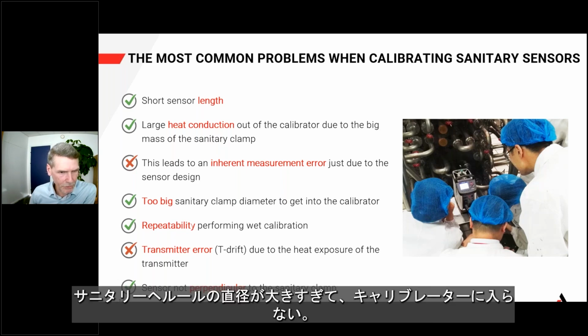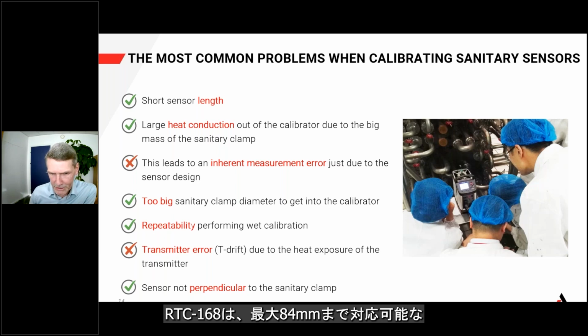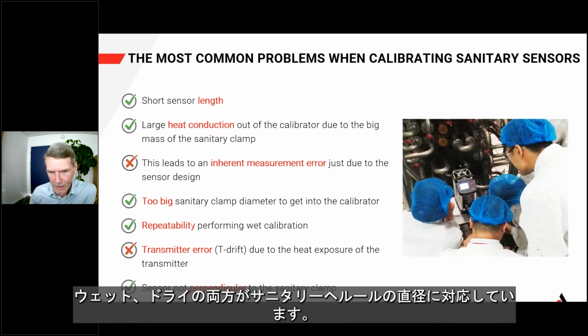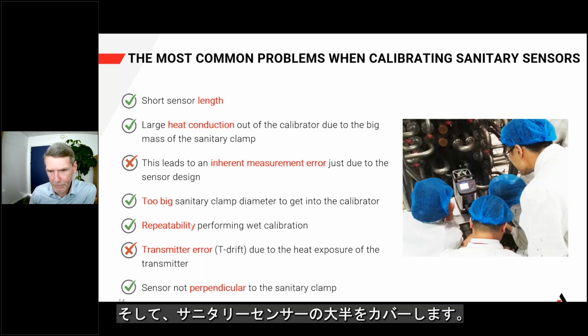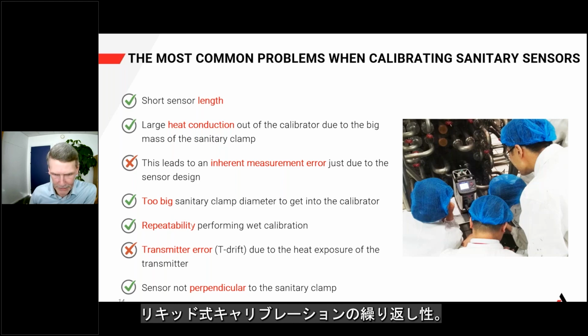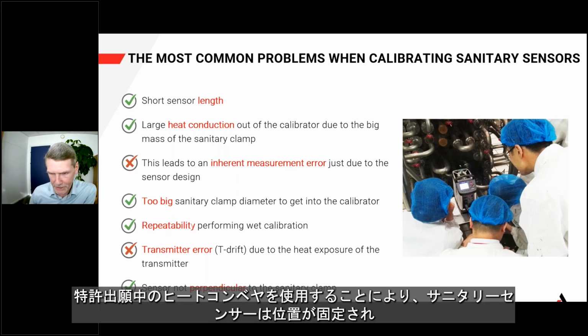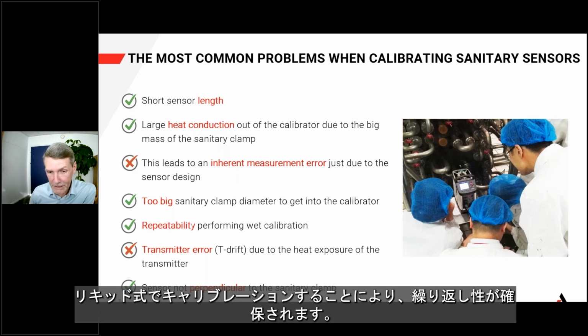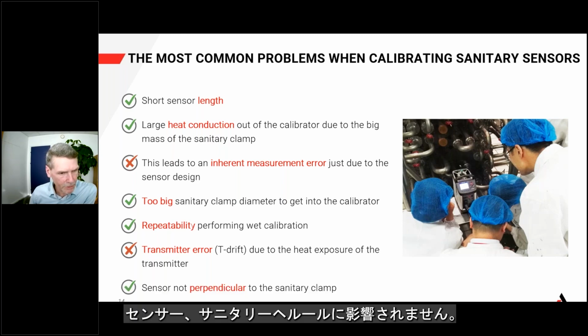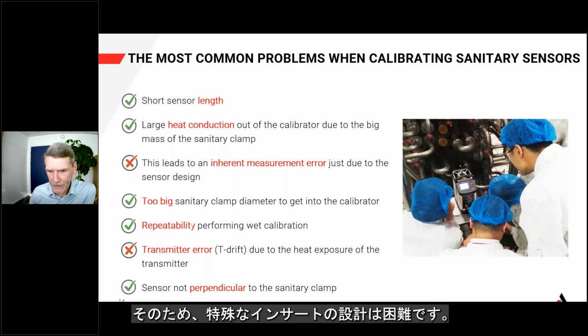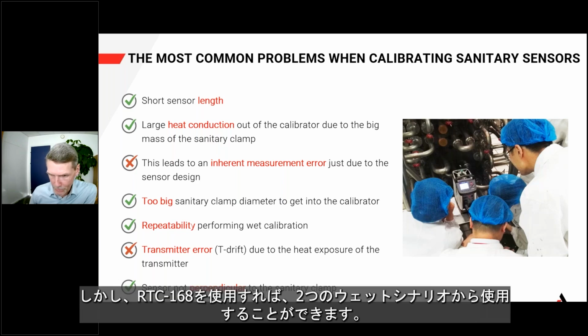Too big sanitary clamp diameters to get into the calibrator. The RTC168 has been designed with a special top, making it possible to accommodate up to 84 mm sanitary clamp diameters, both wet and dry. And this covers the majority of sanitary sensors. Repeatability, performing wet calibration. The repeatability is secured by having the sanitary sensor in a fixed position by the use of the patent-pending heat conveyor. Sensor not perpendicular to the sanitary clamp, then the design of a special insert can be difficult. But with the RTC168, one of the 2 wet scenarios can then be used.